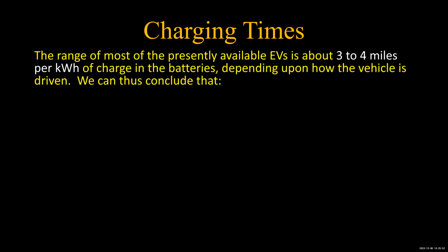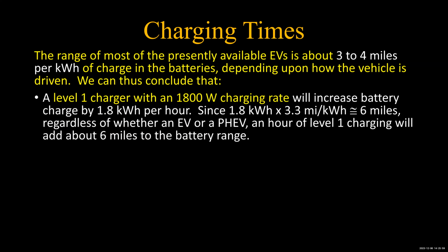But in any case, if we look at 3.5 miles as kind of an average number for EVs, then we can come to certain conclusions. Level 1 with 1,800 watts, that's 1.8 kilowatt hours per hour, okay? And if you take that times 3.3 miles per kilowatt hour, you're looking at about 6 miles an hour of charging. That's another interesting 6 miles an hour, and that applies to how fast you're going, but also how fast you're charging. So for every hour of charging at level 1, you can expect somewhere between 5 and 6 miles of additional distance added to your batteries. All right, and it doesn't make any difference whether you're an EV or a plug-in or whatever, because you're talking about the electric operation of the vehicle. So that's a good number to keep in mind, 6 miles an hour for level 1.